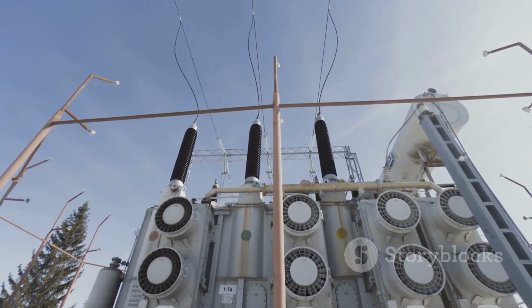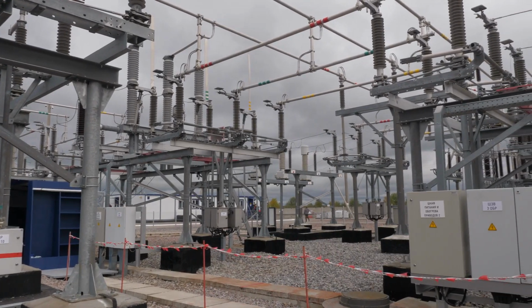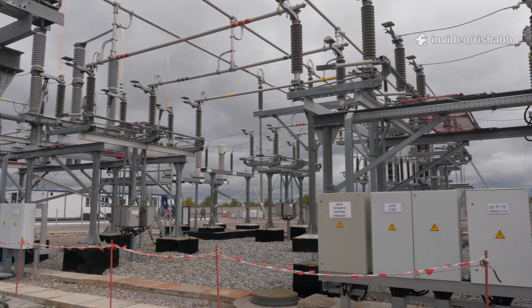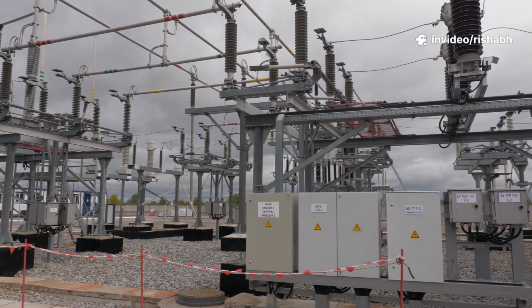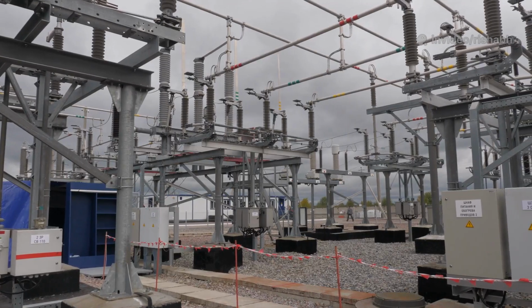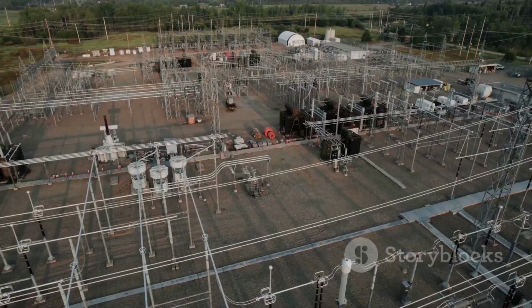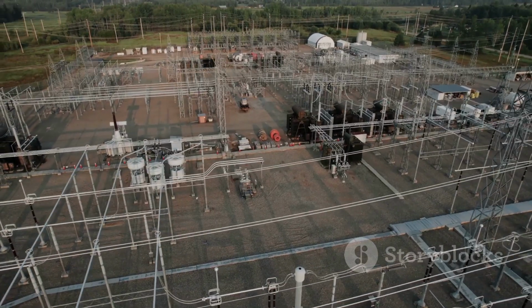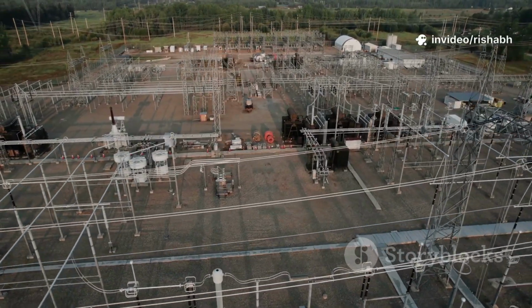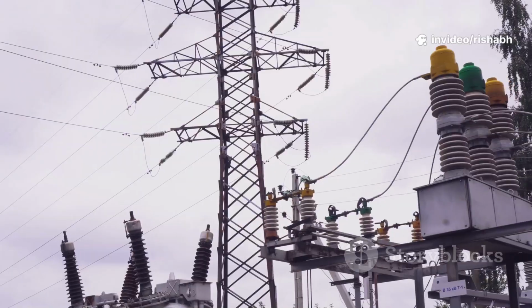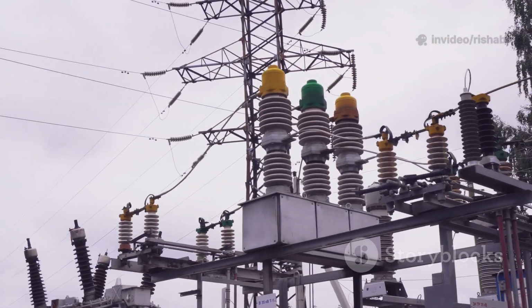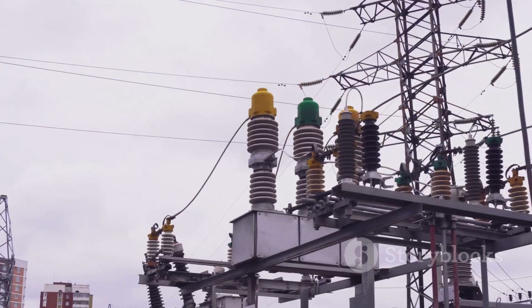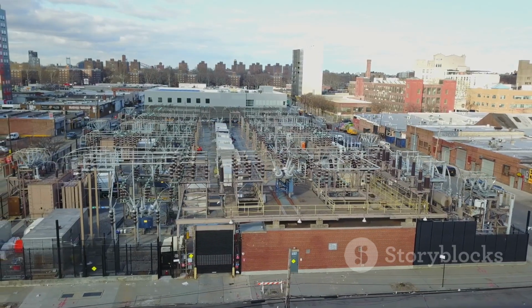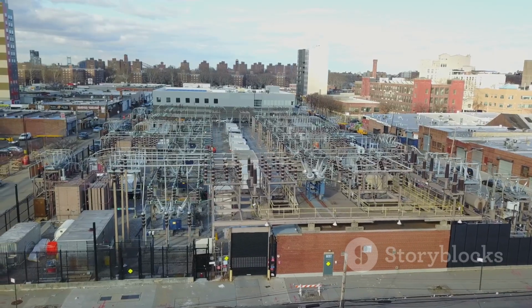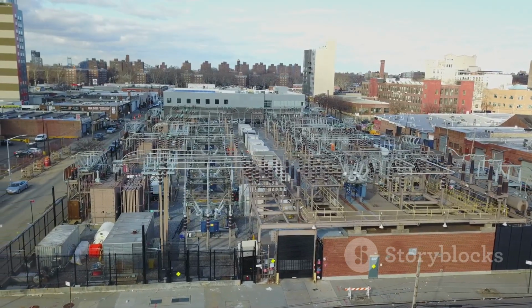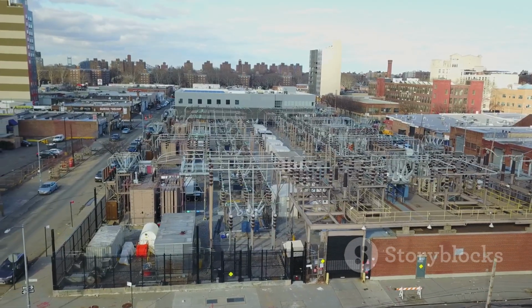Walk into almost any 33 by 11 kilovolt distribution substation, especially across India, Europe, and many other parts of the world, and you will find the Dyn11 vector group specified on the transformer nameplate. This configuration provides the perfect balance of features: a neutral for grounding and single-phase loads on the low-voltage side, harmonic suppression from the high-voltage delta winding, and a standardized phase shift for parallel operation. For these reasons, Dyn11 has become the de facto standard, the most widely used and trusted transformer vector group in medium-voltage power distribution systems worldwide, ensuring our power is both reliable and safe.